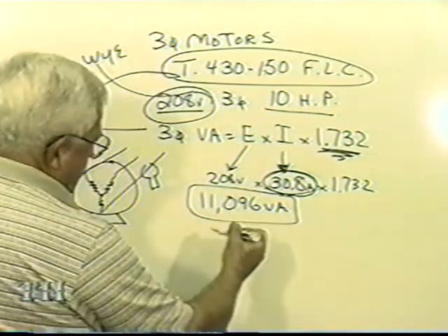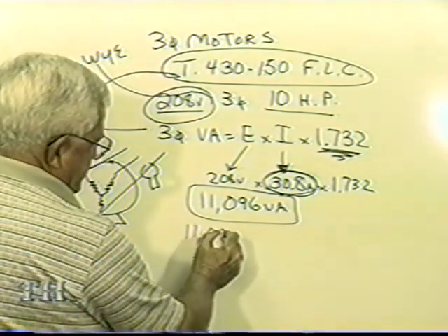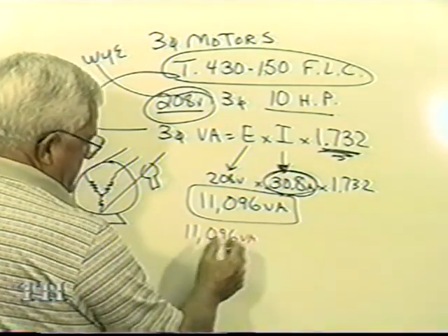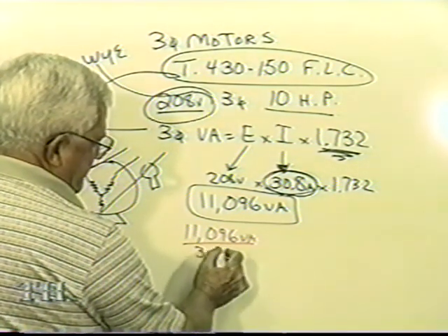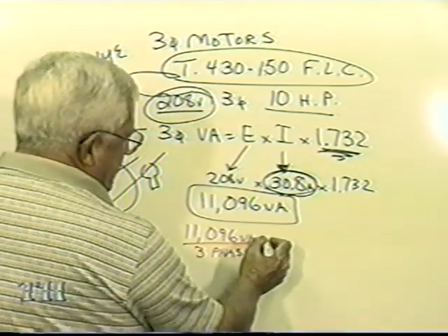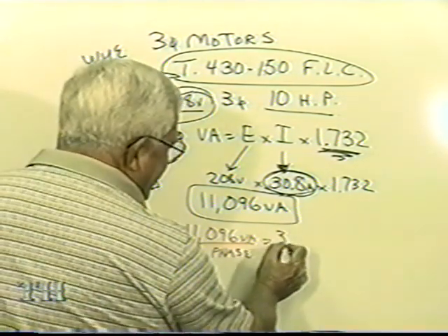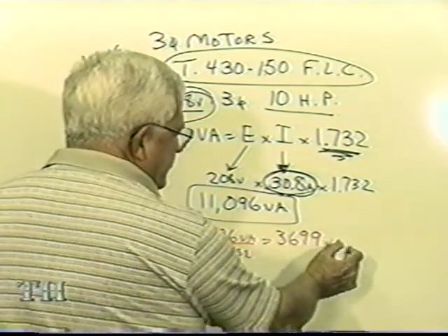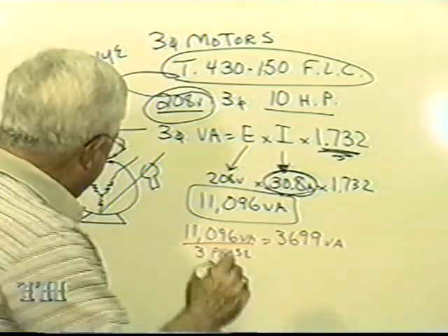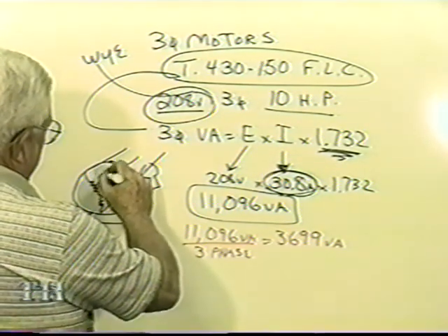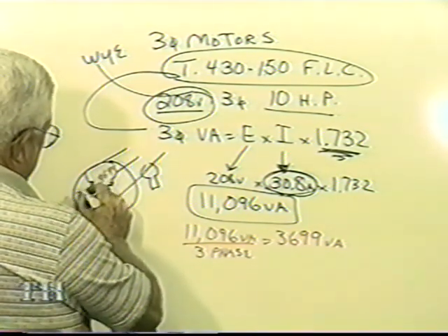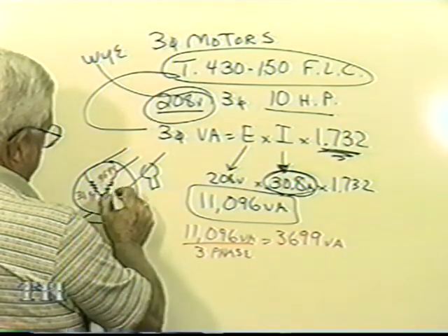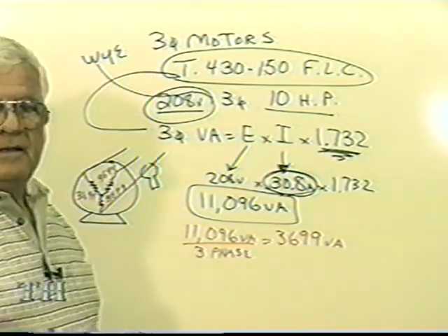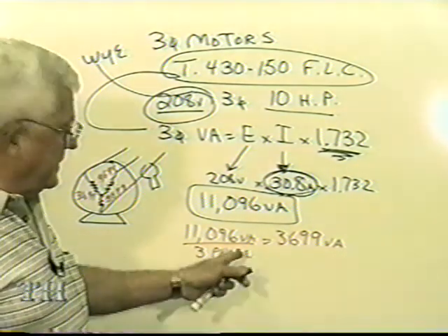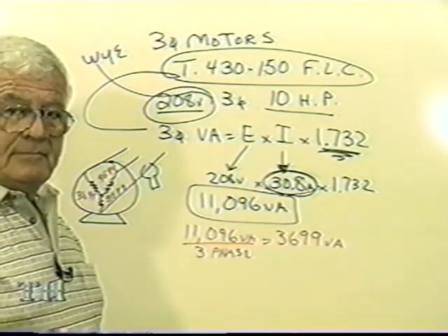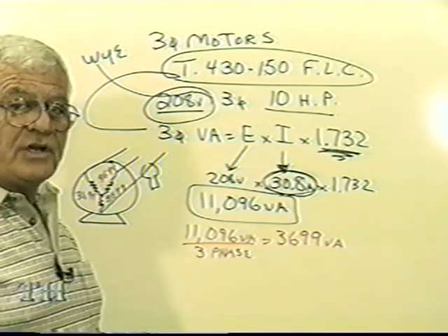What's the beauty of this? If you took this 11,096, which is the total, and you divided it by 3 phases, you would get, rounded up, 3699 volt amps. And if you took the 3699 and put it here, and here, and here, at each coil. In other words, I just split the 11,000 3 ways because there's 3 transformers, 3 coils.